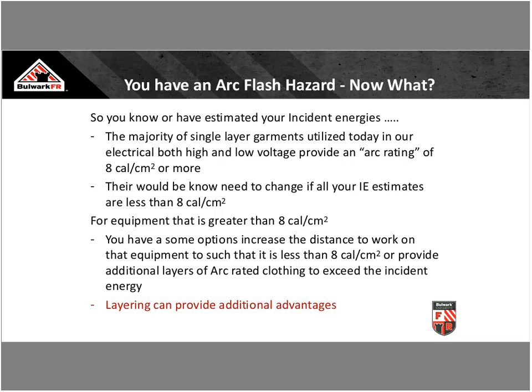So what's the default been for years now? 8 calories or more protection in an arc-rated shirt and pant. The default is Cat 2. PPE Category 2 for 70E terminology, 8 cals or greater on our utility side, and we found that for the most part, that's the large majority of what we do. So what happens when we do this reasonable estimate on the utility side and we do our arc flash assessment on the 70E side and we find out we've got pieces of equipment that need more than 8 calories of protection? Well, on the 70E side, we see that we've got switchgear, we've got big MCCs, and on the utility side, we have our substations, our power generation, where a lot of these higher incident energies are. What do we do?